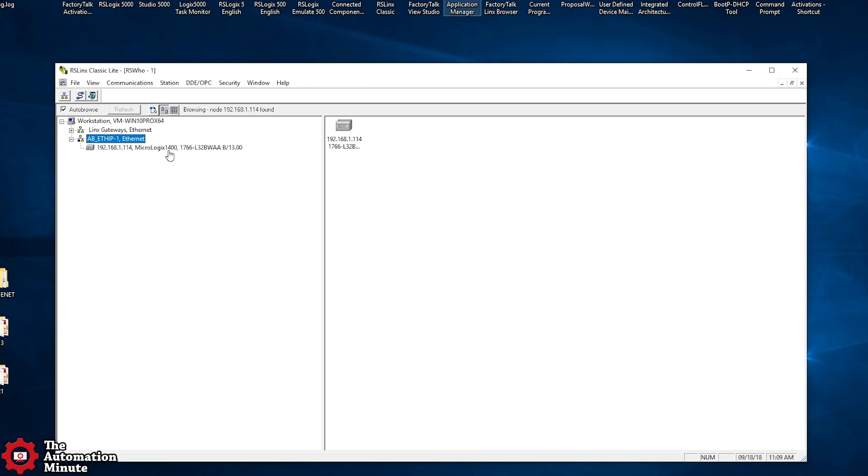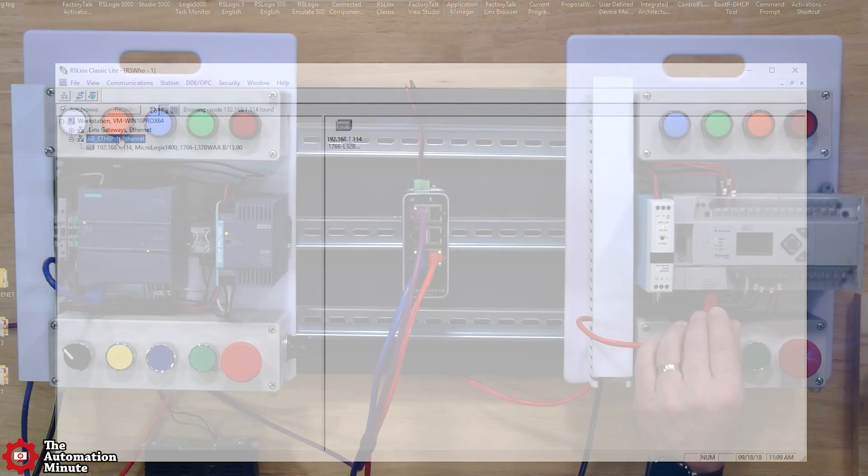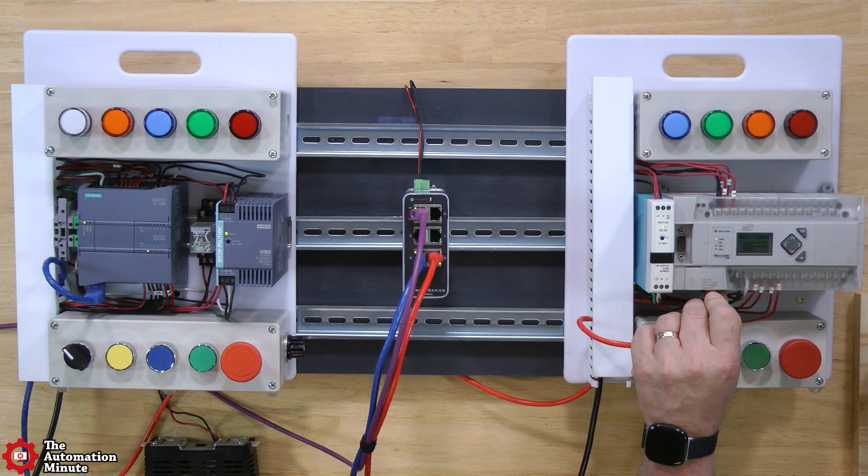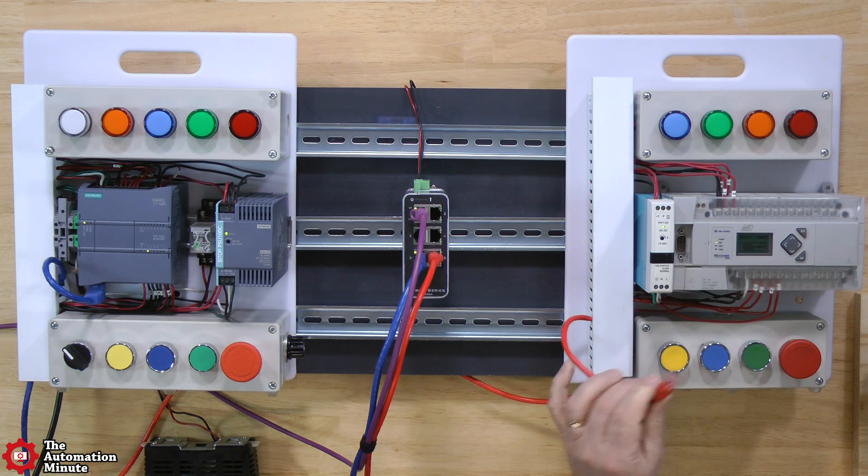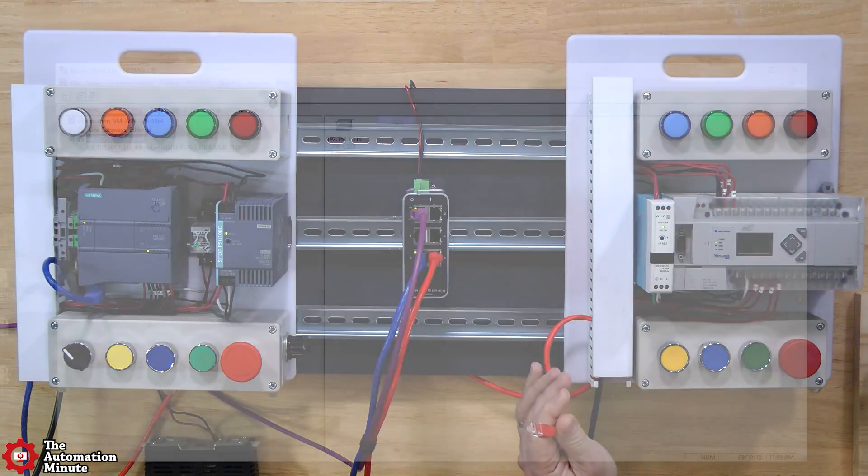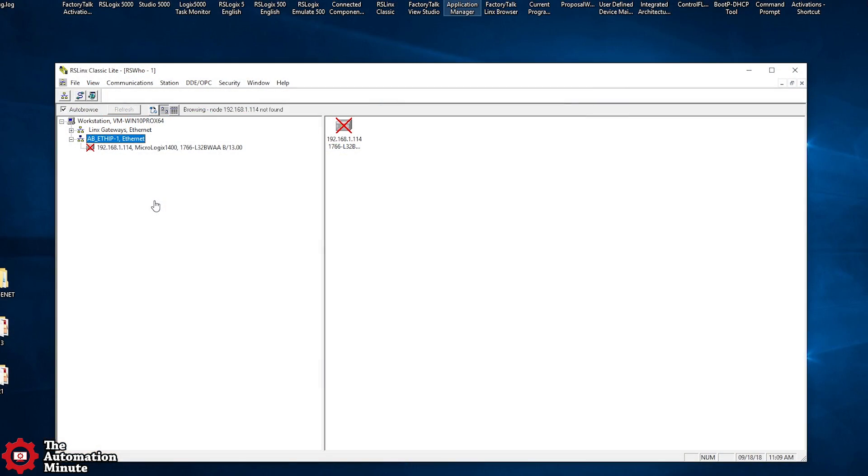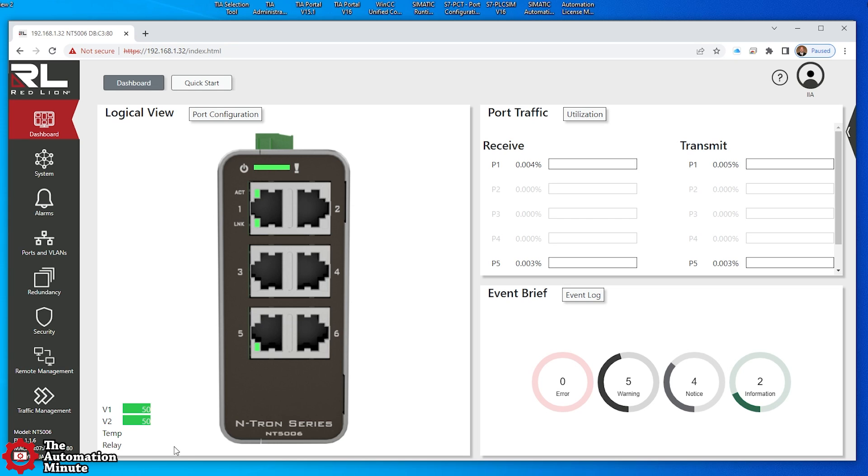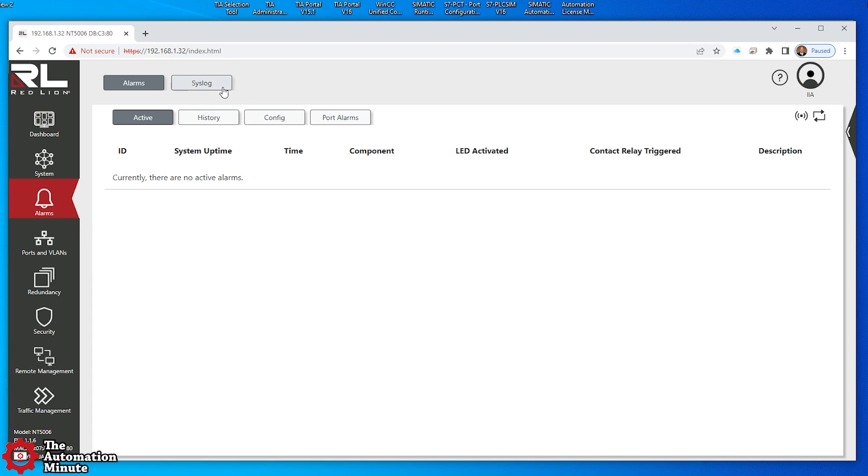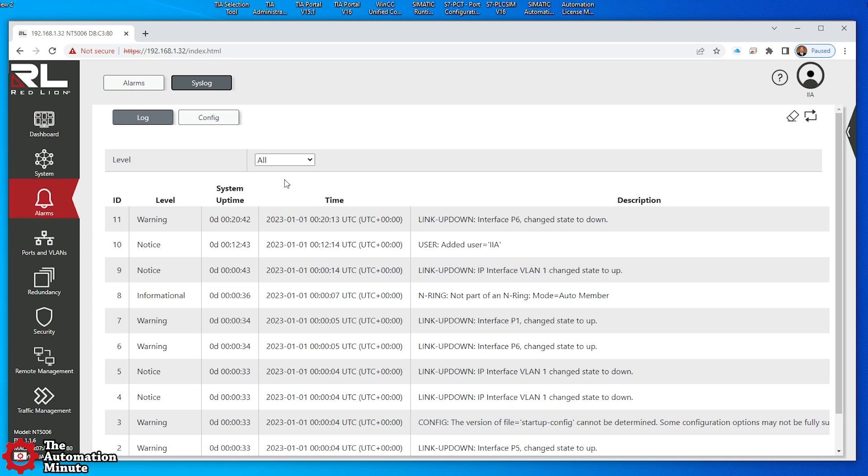Let's switch over to RSLinx Classic. Yep, let me just yank the plug here to make sure that is truly what we're seeing. Okay, it's going out. If I come back here, I should see no more port activity here, right? And then if I go to alarms and syslog, I should see P6 change state to down.